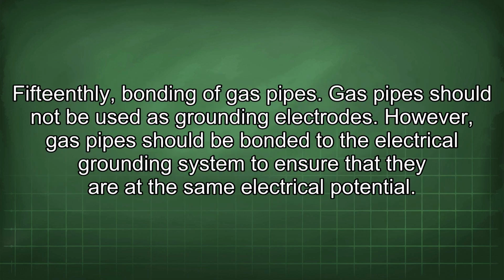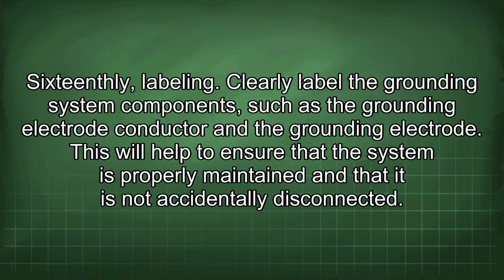Gas pipes should not be used as grounding electrodes. However, gas pipes should be bonded to the electrical grounding system to ensure that they are at the same electrical potential. 16thly, labeling. Clearly label the grounding system components, such as the grounding electrode conductor and the grounding electrode. This will help to ensure that the system is properly maintained and that it is not accidentally disconnected.